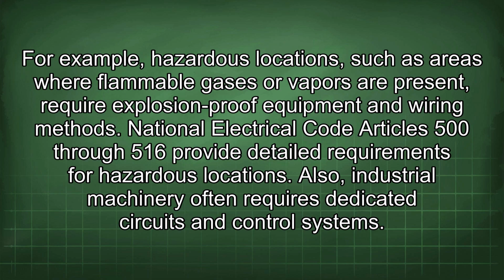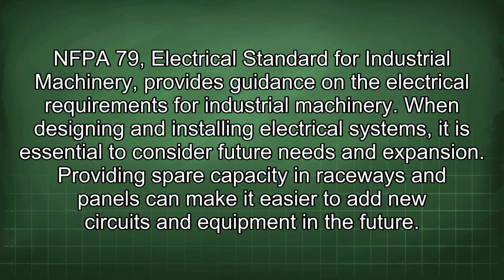For example, hazardous locations, such as areas where flammable gases or vapors are present, require explosion-proof equipment and wiring methods. National Electrical Code Articles 500 through 516 provide detailed requirements for hazardous locations. Also, industrial machinery often requires dedicated circuits and control systems. NFPA 79 Electrical Standard for Industrial Machinery provides guidance on the electrical requirements for industrial machinery.